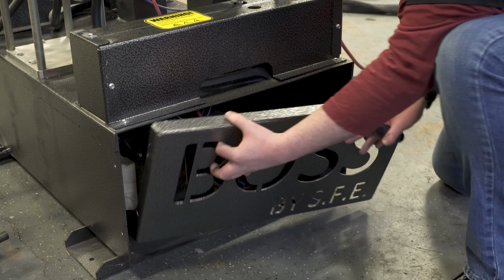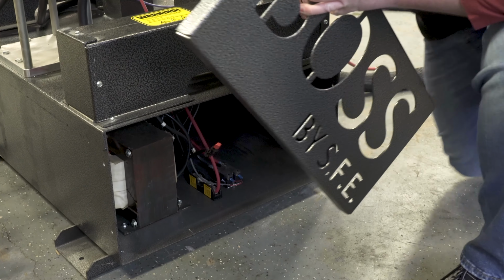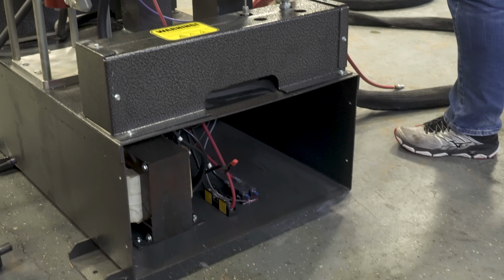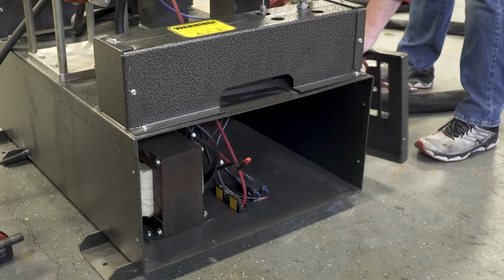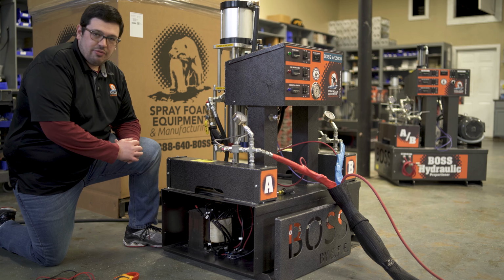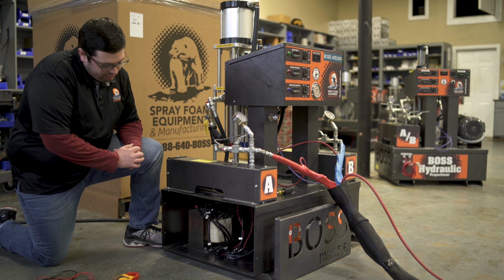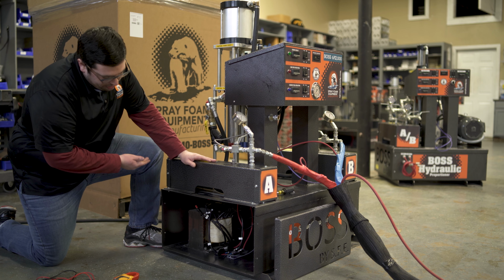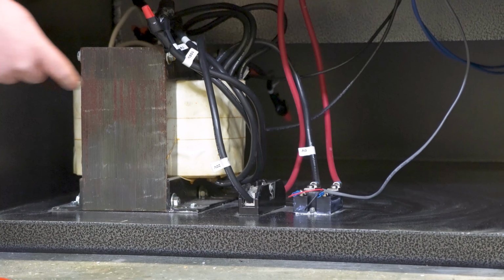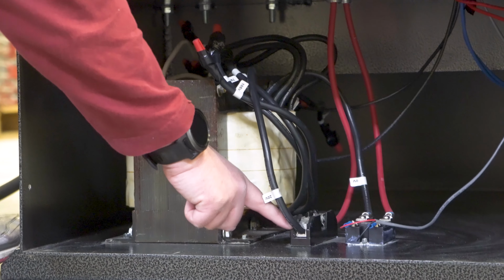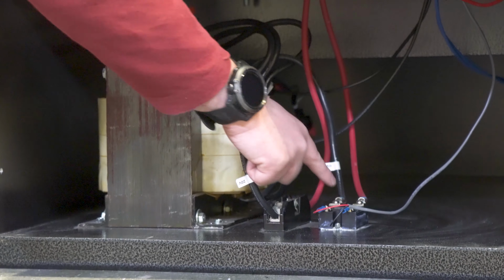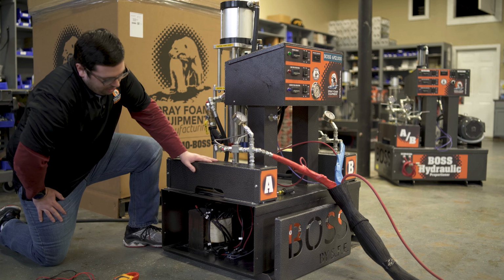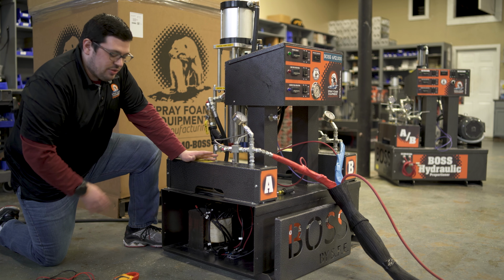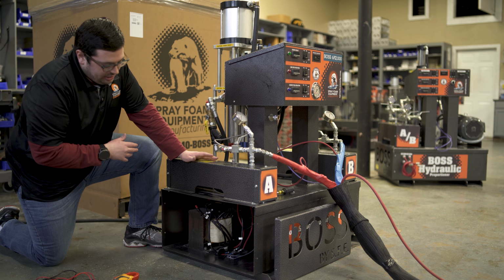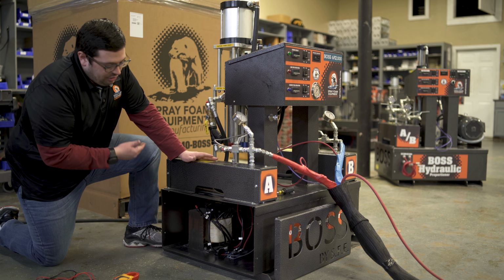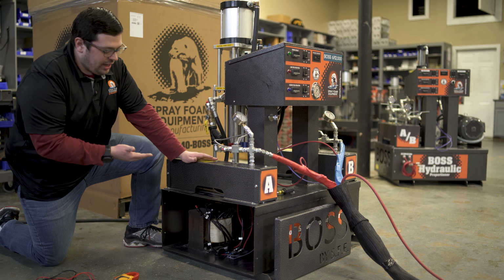But afterwards, you just pull that cover straight out, and it'll reveal all the components, the hose heat components, that are in the lower portion of the machine. All right, the first thing you'll notice once we have the access cover off is obviously 3 main components, or 4, for your hose heat system: the transformer itself, the fuse holder and fuse, and the solid state relay. Now the first thing you want to identify is which voltage options are connected from your transformer to your fuse and relay, because that determines how much voltage you're getting out of your machine.